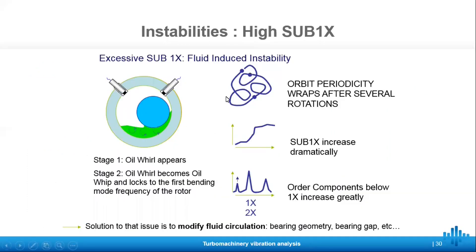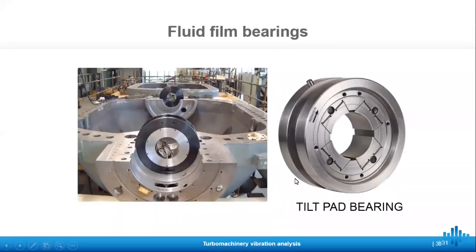Regarding the sub-1x or subharmonics, if we have any fluid instability, we can notice two stages. Stage 1 is where the oil whirl appears, and stage 2 is where it becomes an oil whip and locks the first bending mode to the frequency of the rotor. The consequence will be a complex orbit, and the sub-1x will increase dramatically. In the order spectrum, we will be able to see the order components increase as well. A solution could be to modify the fluid circulation, possibly by changing the bearing geometry — an example of this being done can be seen in the tilt pad bearing, which consists of pads that are free to tilt, allowing the oil to create a self-sustaining film.